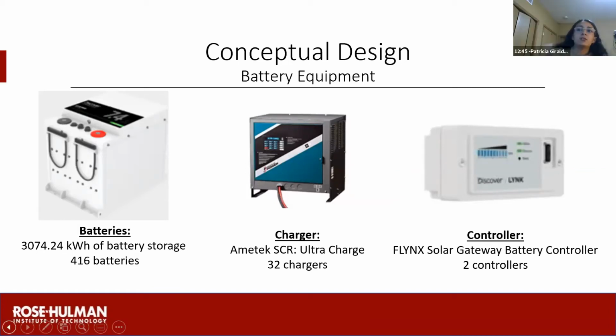The amount of energy sold back cannot exceed the daytime minimum load at any 15-minute interval. This amount was found to be around 2,326 kilowatts by running a base case power flow model. So in order for our distribution system to stay within this limit, the team calculated the amount of battery storage we would need to be around 3,074.24 kilowatt hours. So in order to have this much storage, we need 416 of our 7.4 kilowatt hour batteries. And that's 32 parallel strings of 13 batteries.